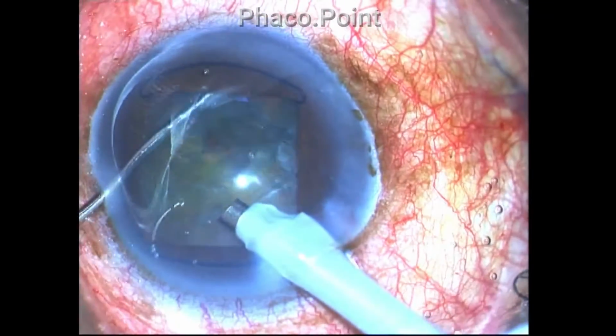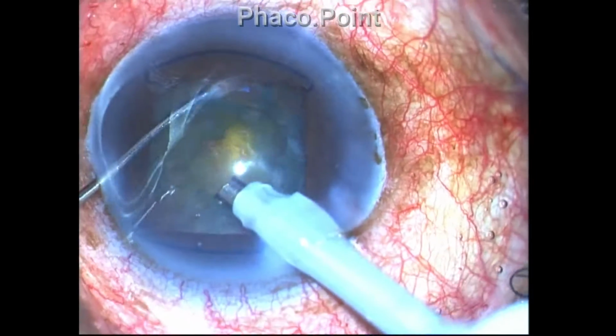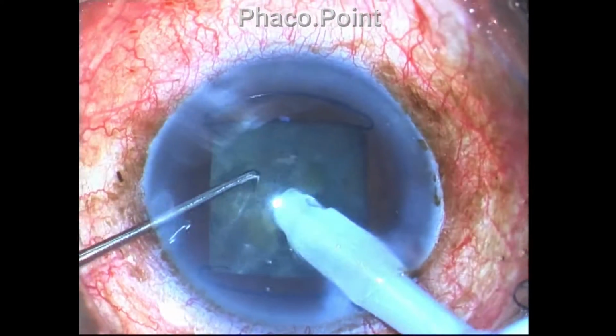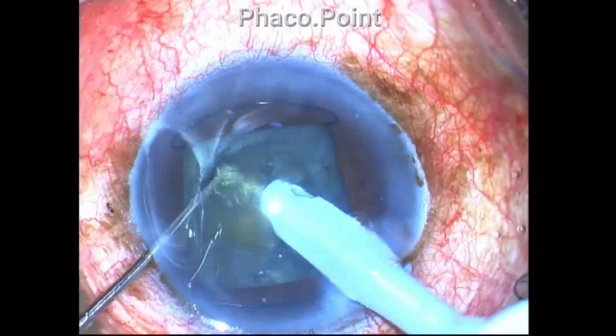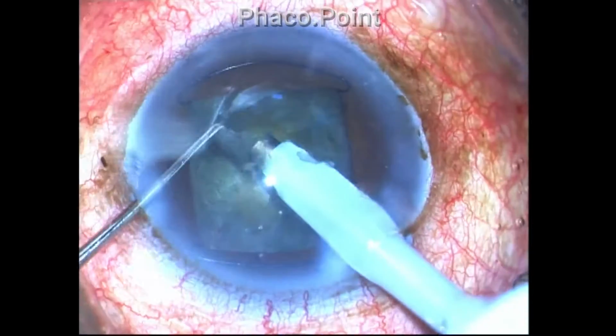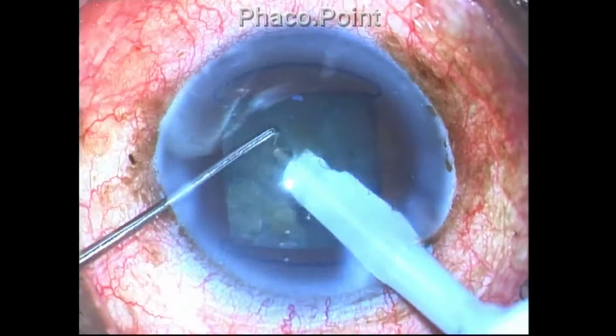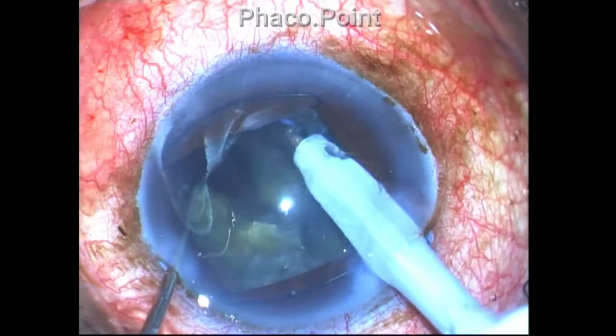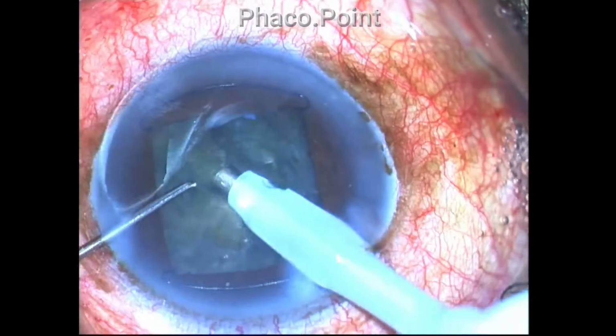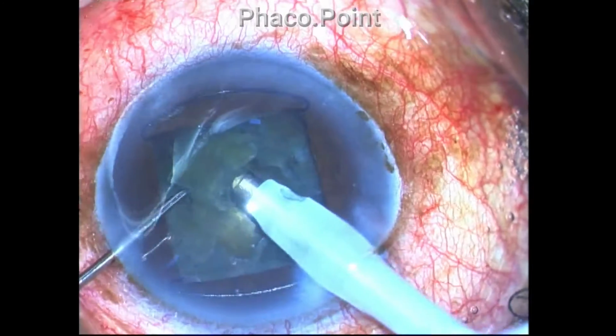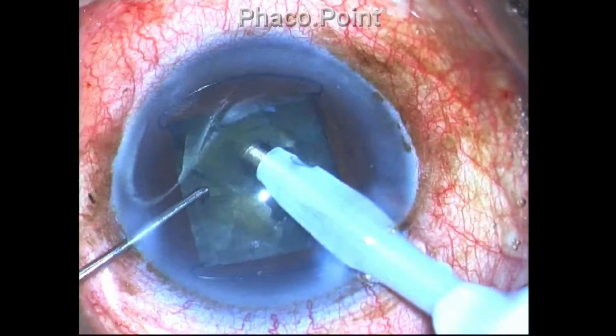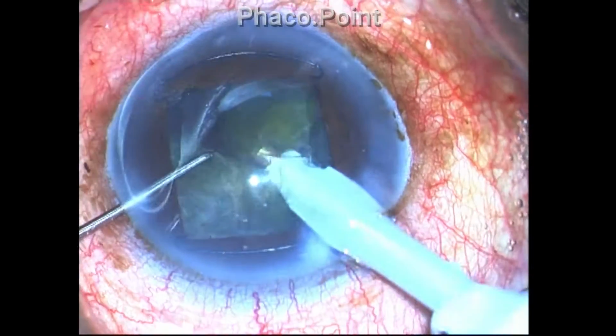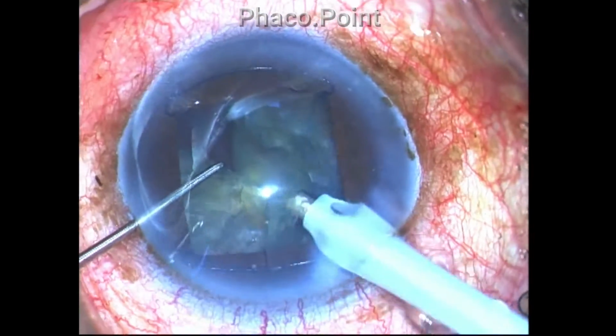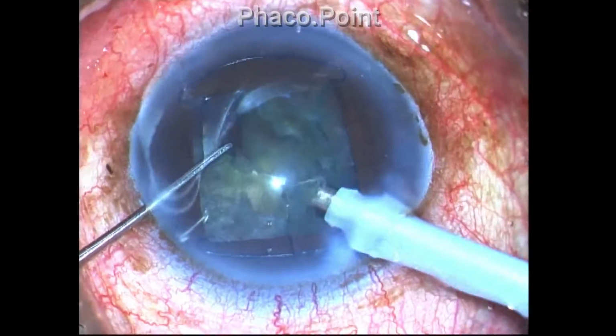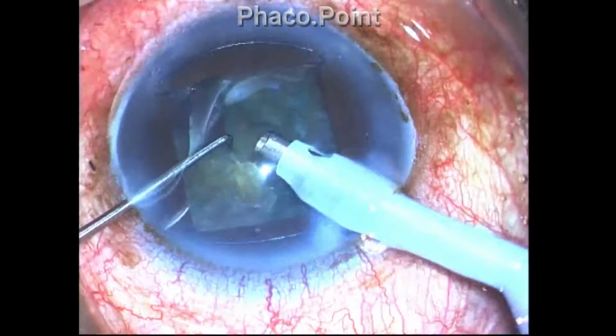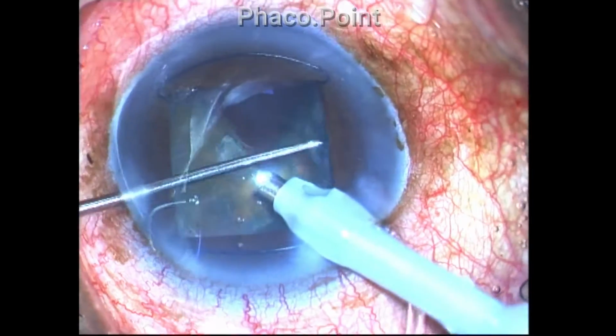Now this is possible with a dual linear foot pedal system. You can vary the vacuum levels for a given power level, whereas in other systems you need to enter foot pedal 3 only after working through the full preset vacuum. So one of the fragments is removed and the procedure is going in a predictable fashion.